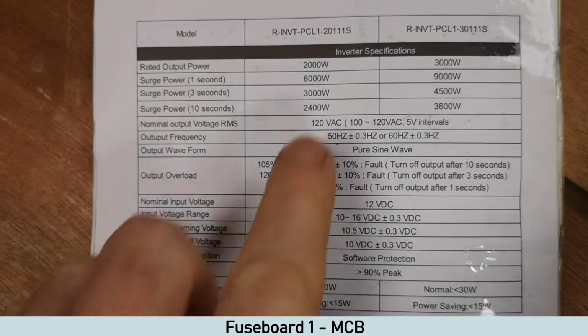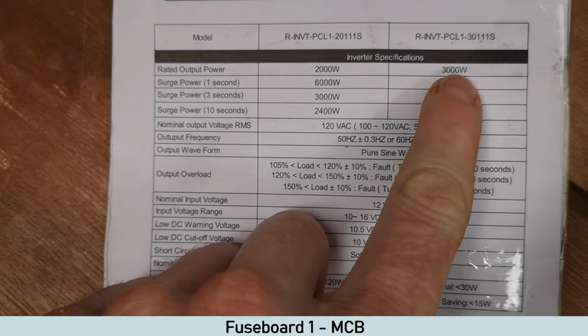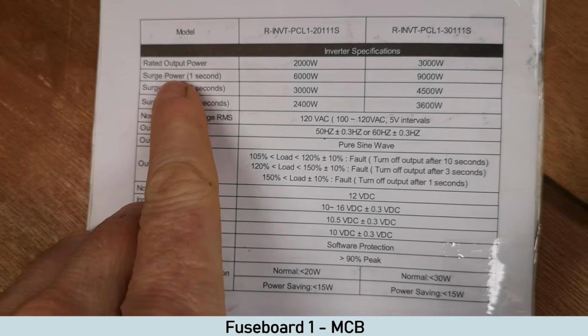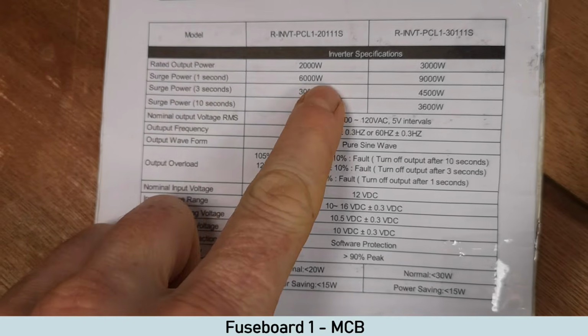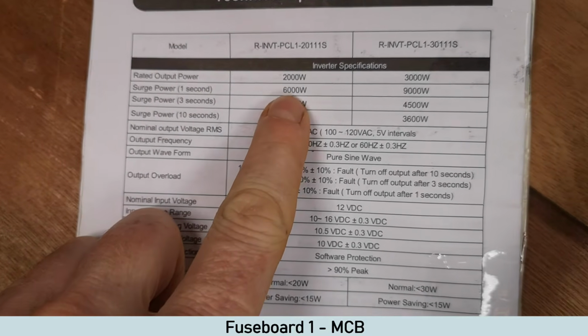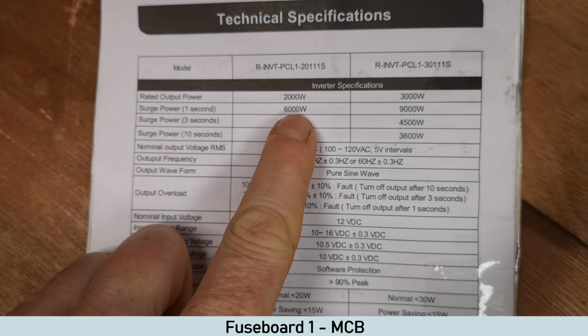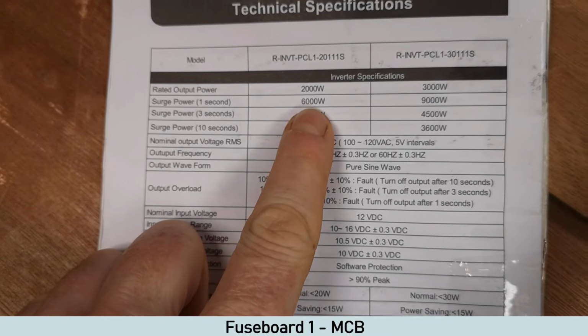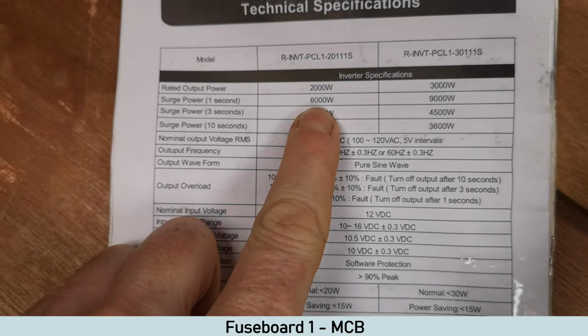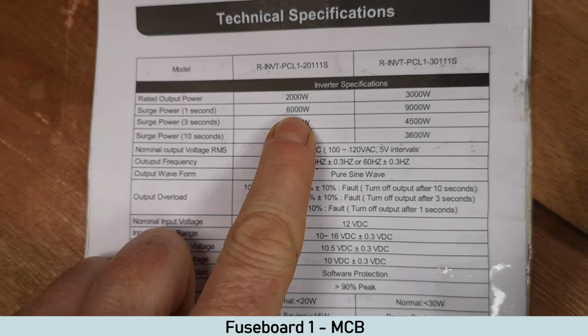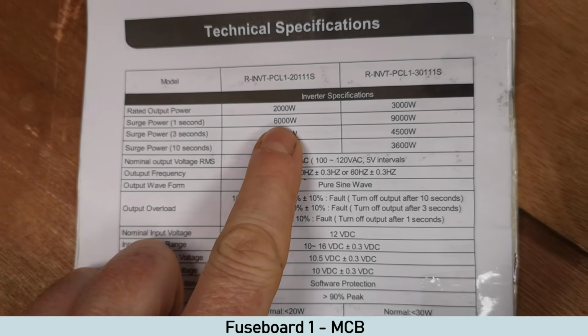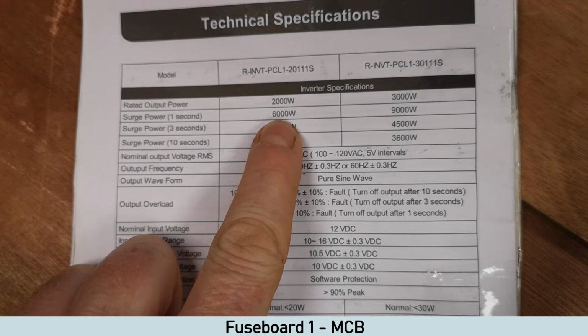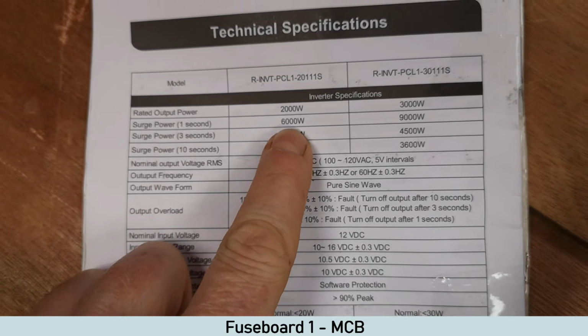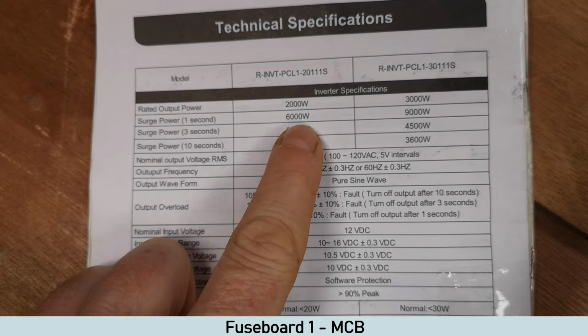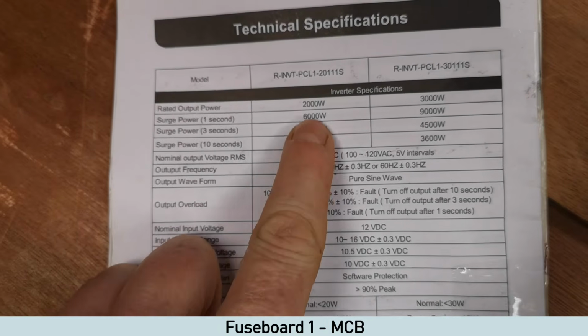Now you'll notice in the manual here that, so obviously there's a 2000 watt model, 3000 watt, that there is a surge power. So the max surge power for the 2000 watt is 6000 watts potentially. Now obviously that's what it can withstand. It doesn't mean that when you turn it on it's going to pull 6000 watts. It all depends what's plugged in. So I mean 6000 watts at 230 volts is 26 amps. So it's going to trip our breaker out. Now the reason we've still got 10 amp is because we're never going to pull this amount.